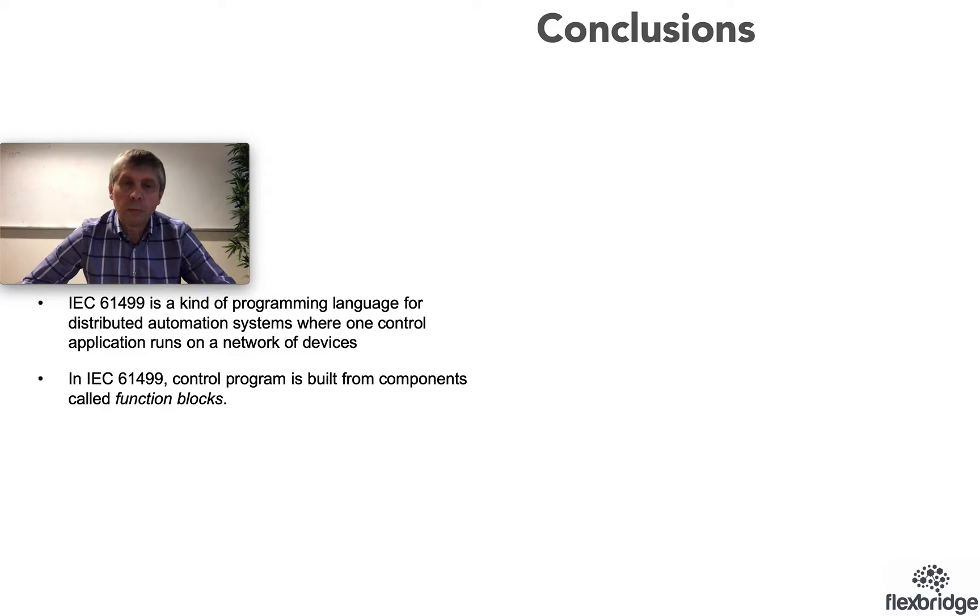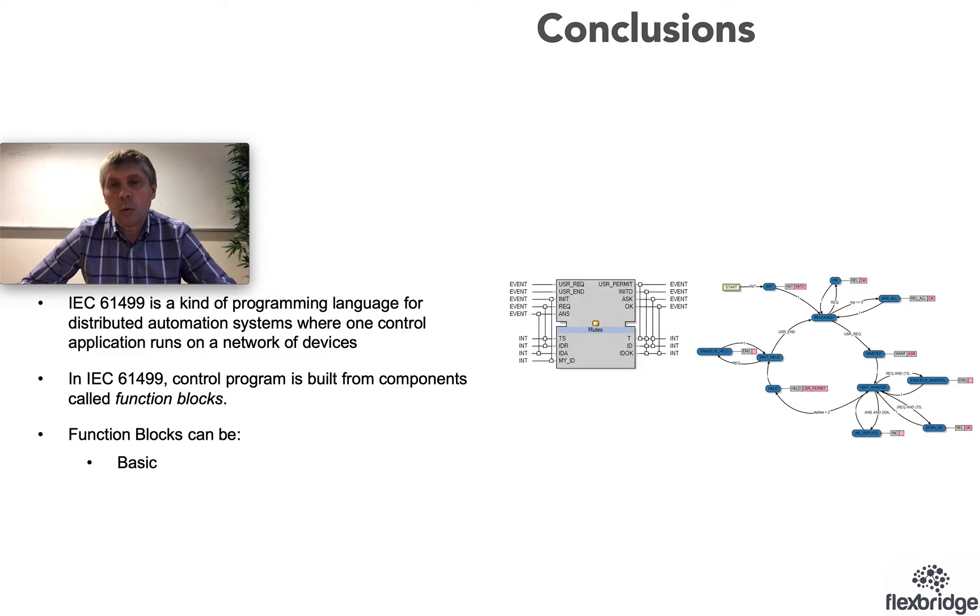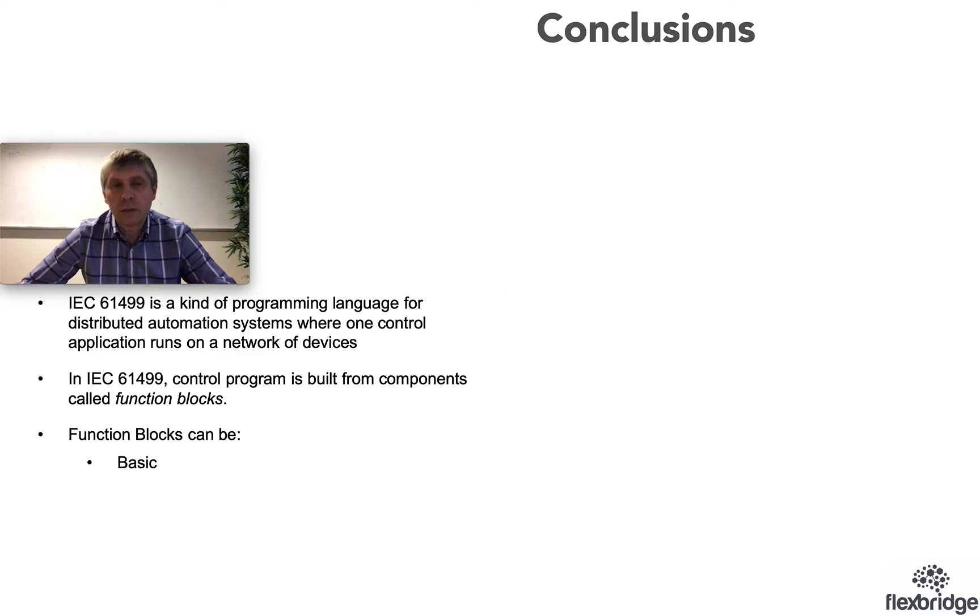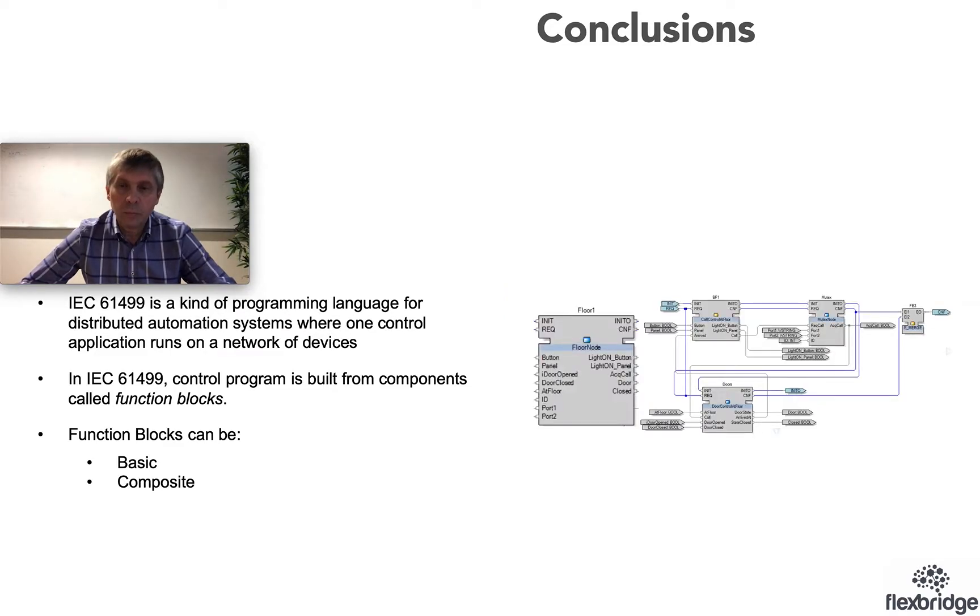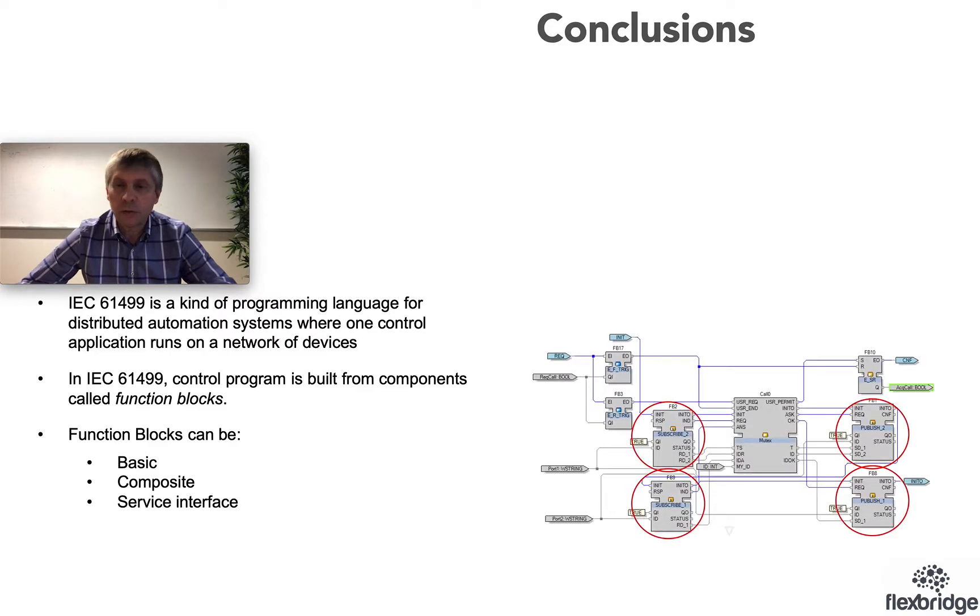Function blocks can be basic, where the block is defined as a state machine, can be composite, where the block is defined as a network of other function blocks, and can be a service interface, where service interface function blocks are usually provided by vendors of devices and application developers just use them from the library without seeing what is inside. They are usually written in some other way not approachable by application developers.